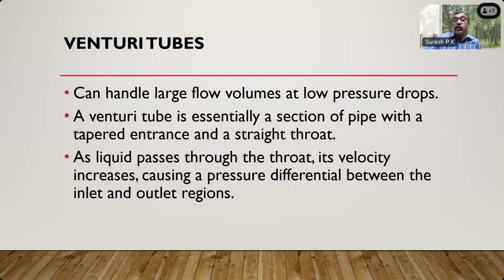I think you understand that a venturi has a gradually decreasing area. Therefore, the pressure drop across the venturi will be less than the pressure drop across the orifice. So the operating cost will be less, but the cost of the venturi tube can be more. So you will decide which one you need.